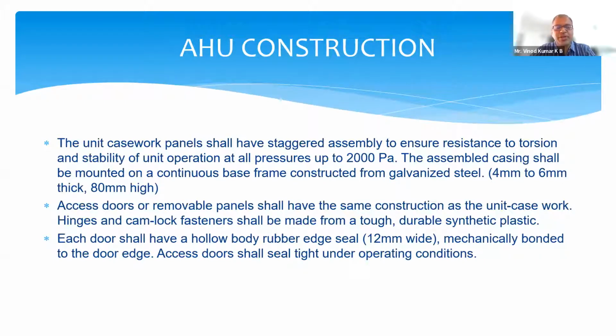Secondly, the doors should have enough rubberized seal so that they don't leak. If after this session you go and check any of the AHU rooms, you can see air leaking out of the AHUs. The problem is between different sections of the AHUs where thermal bridging is not done, where the sealant is not correct, plus wherever access doors or removable panels are there, those sealants are not there, which means you're going to lose a lot of treated cold air.